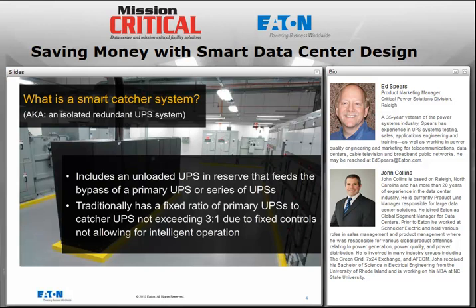And traditionally, these type of systems have been designed with either one catcher for one UPS or maybe at a maximum one catcher UPS supporting up to three primary UPSs. And that's a little bit restrictive, but due to the fixed controls and the lack of intelligent operation, that was about as big as that type of system could get. And in very large installations, that's not quite enough.